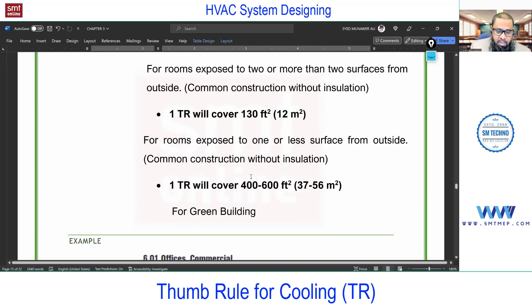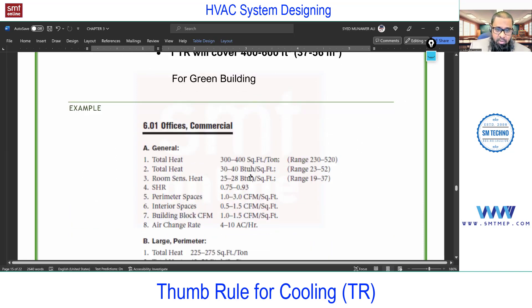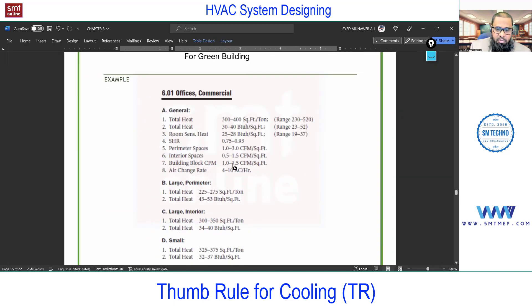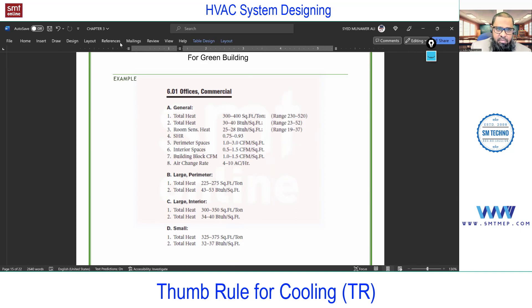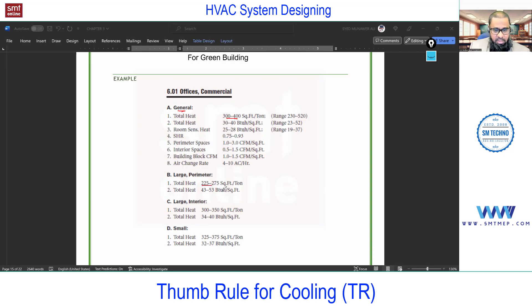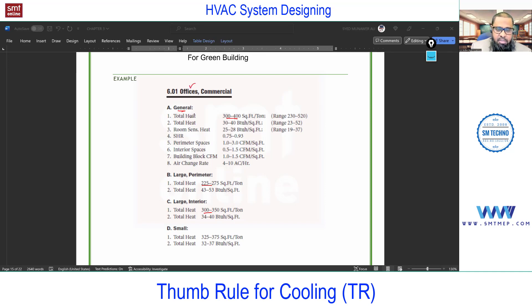At this level, just memorize these thumb rules — they may be asked in interviews. From the Rules of Thumb handbook, which can be used at the initial stage of design: for a general office, the value is 300 to 400 square feet per ton. For large perimeter spaces, it's 225 to 275 square feet per ton. For large interior spaces, it's 300 to 350 square feet per ton. This handbook covers rules of thumb for different applications — offices, hotels, schools, and more — organized by section. This is just an example; we'll refer to it during the calculation stage.